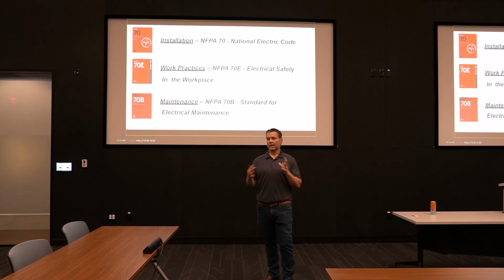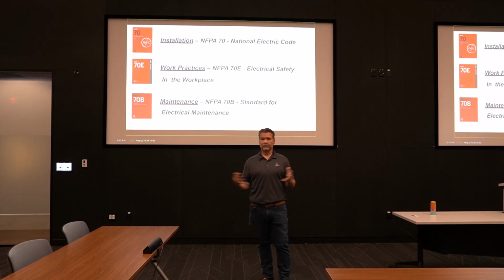You know, when it comes to arc flash, there are two basic things that will save you. Distance, the further away you are, the safer you are, and then time. An arc flash is going to continue to grow as long as that energy source is there to feed it. So when is that breaker going to trip? When is that overcurrent protective device going to open? And if they're not properly maintained, it may not open in the time frame that the arc flash label believes it's going to. So NFPA 70B is a big step forward in creating some more safe work practices for us.